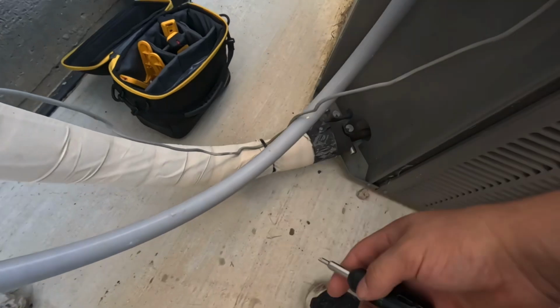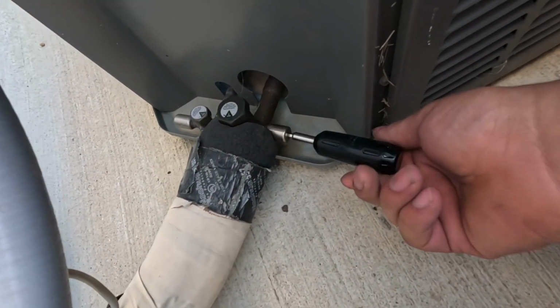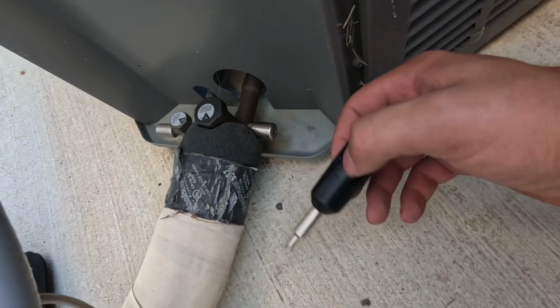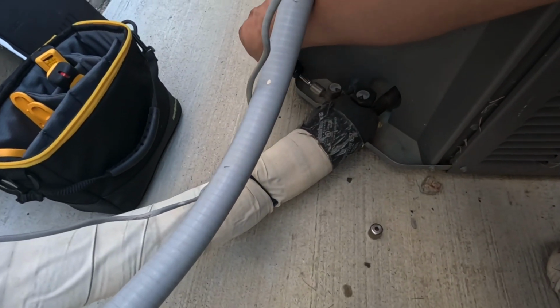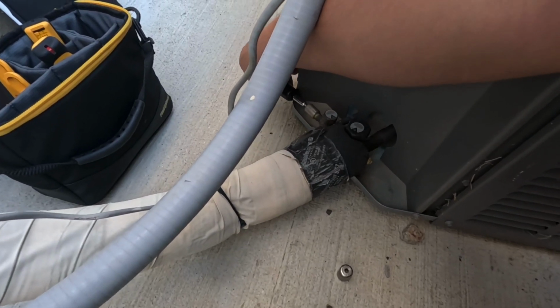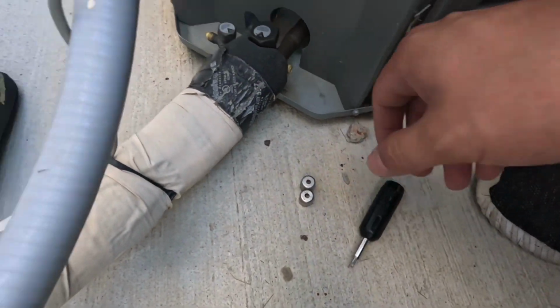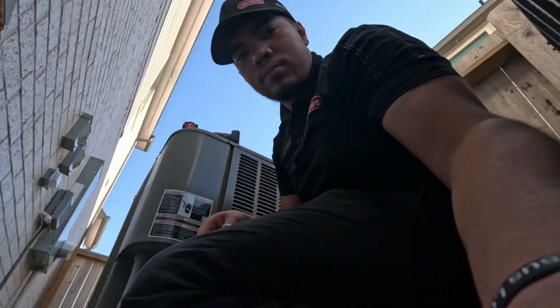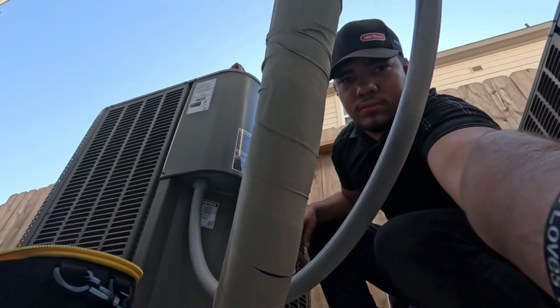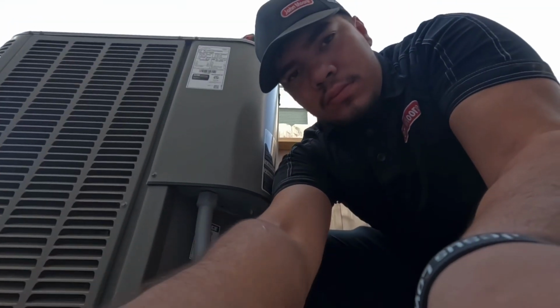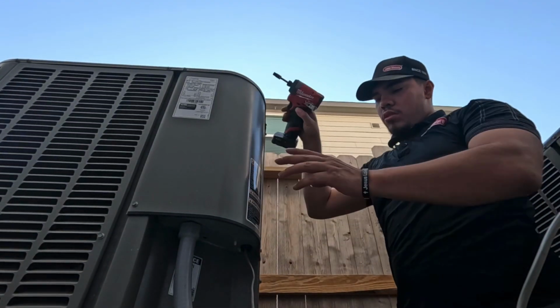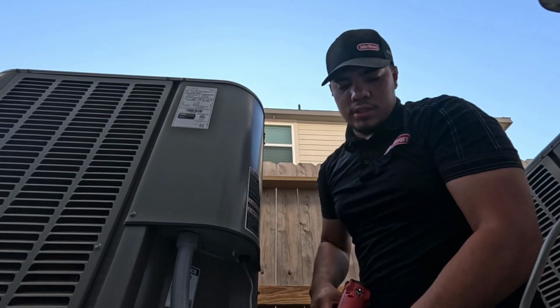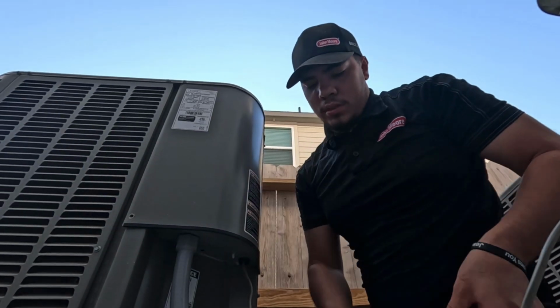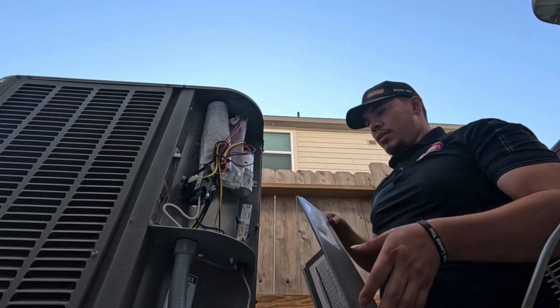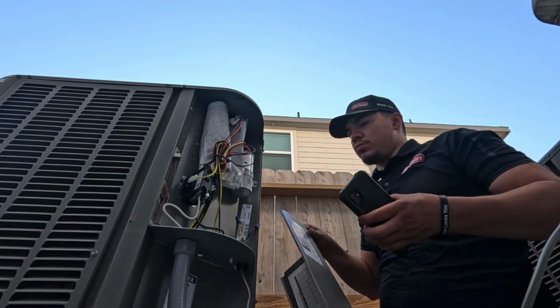So this is a key for these caps right here. These are called locking caps. Go ahead and open this up real quick. Okay, so this is the condenser right here. I'm going to open this panel right here and check the amps on the compressor and the fan to make sure they're at proper amperage and they're not overamping. It looks brand new, so I don't think it'd be overamping, but still, we got to check.